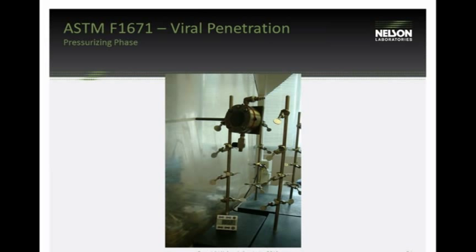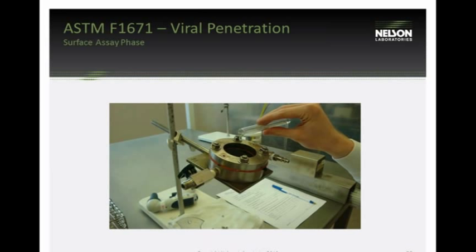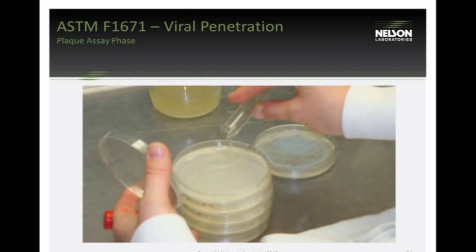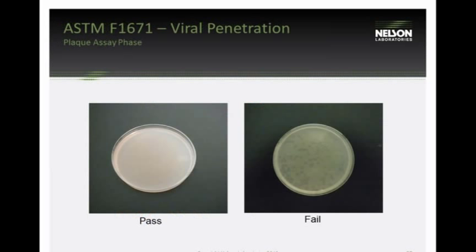At the end of the hour, the challenge is drained from the test cell. Sterile nutrient broth without virus is applied to the non-test side of the sample and swirled for one minute to recover any virus that penetrated through. That nutrient broth is recovered and placed in a test tube, then plated with E. coli and top agar and incubated overnight. If only E. coli grows, it's a pass; if plaques appear, it's a failure.